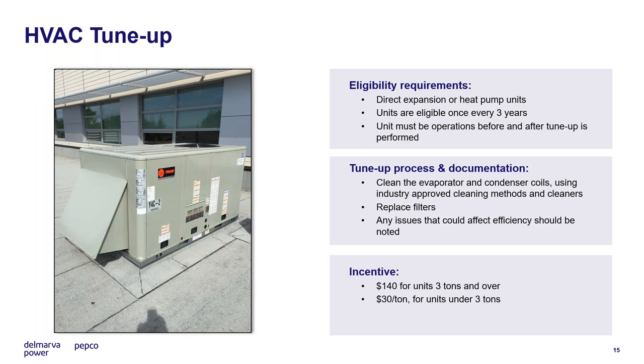What happens during this is maybe your in-house staff, or yourself, will do some minor efficiency measures: clean the evaporator and condenser coils, use industry-approved cleaning methods and cleaners, replace filters, and note any issues that could affect efficiency. Once those are performed, the unit should be operating more efficiently. We pay out $140 for units 3 tons and over, and $30 per ton if the unit is 3 tons or less.